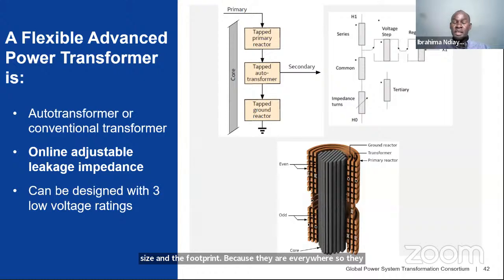So what we call a flexible transformer is an interconnection transformer that has an adjustable leakage impedance. Transformers have been here, as I mentioned, for close to a century now. They have never been known as having the capability to vary their impedance. We came up with that breakthrough, and this figure explains how we went through it.